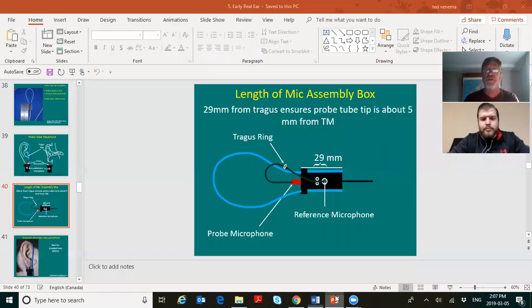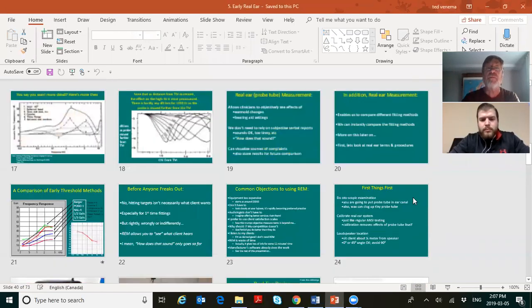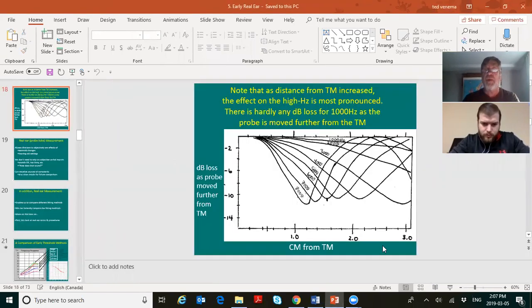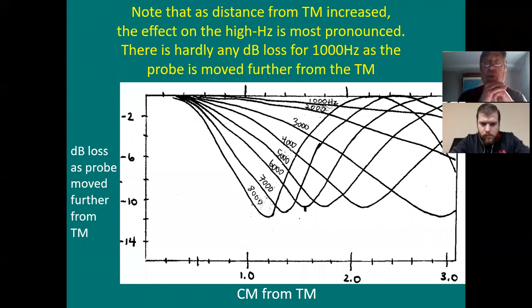Now there's a picture here I want to show, and we did last time, but by gum we'll do it again. When you're looking here, this is showing you the effect of probe tube placement. The horizontal axis indicates the distance of the end of the tube from the eardrum. 1 centimeter, 2 centimeters, 3, which is an inch, okay? And what do you lose? This vertical axis shows the decibel loss as the probe is moved further from the tympanic membrane. Note that as the distance is increased, the effect on the highs is most pronounced. There's hardly any loss for 1,000 hertz. Look at this. Almost nothing happens for 1,000 hertz. When you're looking at 8,000 hertz, you move that tube any distance away from the drum and you've lost it.